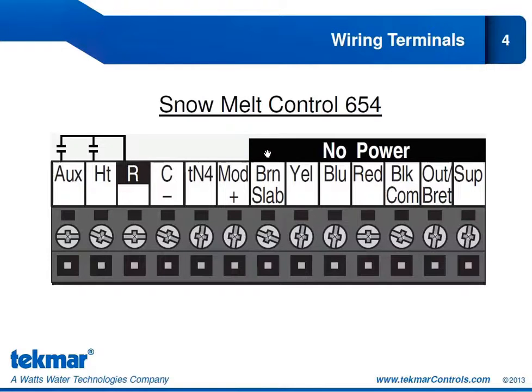Now, if we move past the sensor inputs, we have our plus-minus modulating output that can go to a mixing device or to a mod boiler. So this is the 0 to 10 volt or 4 to 20 milliamp modulating output. We also have our TN4 connection. So yes, this is a TN4 compatible snowmelt control that you've all been anxiously waiting for. You can see over here we have 2 additional relays, an auxiliary relay and a heat relay. And I want to point out that both of these are tied to the R. So the heat relay would be operating your boiler, and the auxiliary relay is going to be operating an alert device or a system pump.